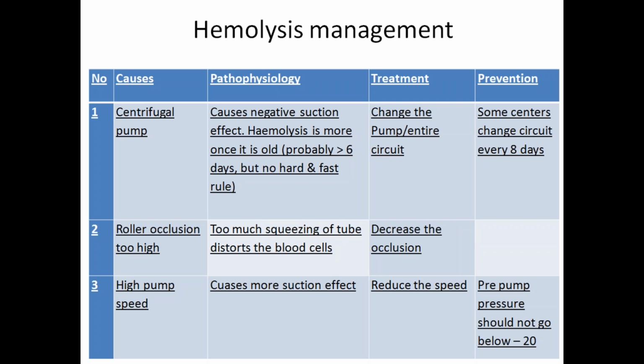So it's better to do these things in the daylight hours when all the people are around. Have your pump head ready and primed, and go on a full ventilation, maybe with inotropes and everything ready, and then stop the circuit and go on that, change the pump head. And if you're really careful, if the perfusionist is experienced, it doesn't take more than 3 or 4 minutes to change the pump head.